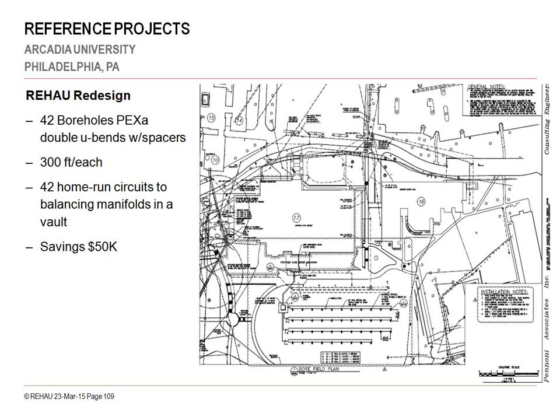And you had the ability of going in and isolating down to a single borehole if there was ever an issue, say borehole 25, and shut off just one borehole and marginally impact the performance of the field, as opposed to the original design, where if you had a leak, you could only isolate down to a circuit of 10 boreholes. You'd have to shut off that complete circuit while researching, trying to find the leak.